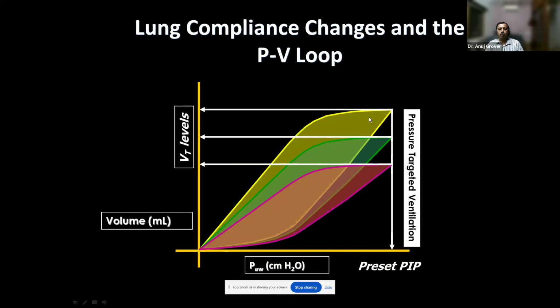As this loop rises up, for the same pressure you are getting higher tidal volume. That's what we need to be wary about. Think of reducing the pressure. Once your tidal volumes are better, reduce the pressure. You don't want to exceed that tidal volume here.